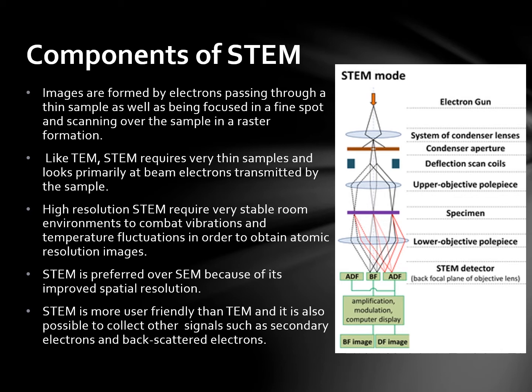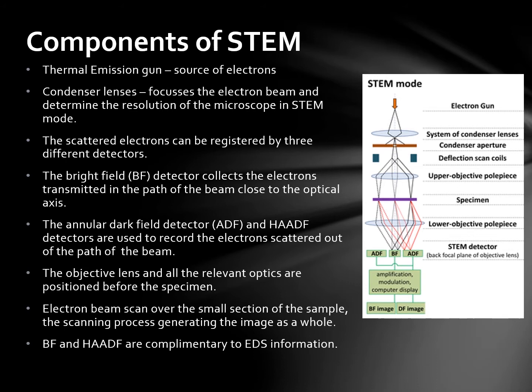The thermal emission gun is the source of the electrons. The condenser lenses focus the electron beam and determine the resolution of the microscope in STEM mode. The scattered electrons can be registered by three different detectors. The bright field detector, abbreviated as the BF detector, collects the electrons transmitted in the path of the beam close to the optical axis. The annular dark field and high angle annular dark field detectors are used to record the electrons scattered out of the path of the beam. The objective lens and all the relevant optics are positioned before the specimen, and the electron beam scans over a small section of the sample; this scanning process generates the image as a whole.